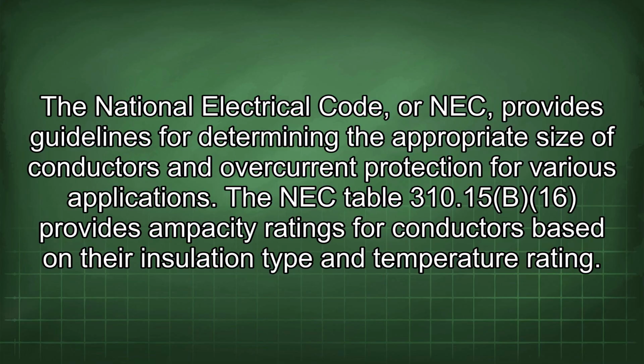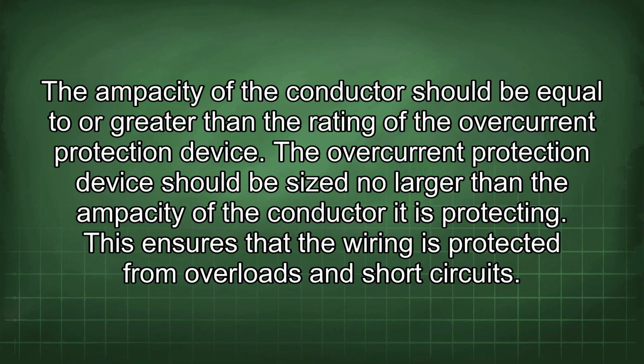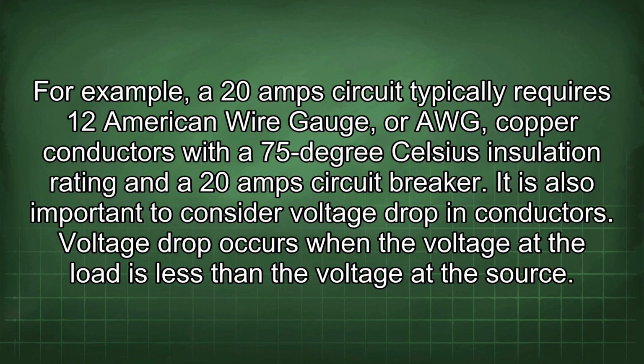310.15(B)(16) provides ampacity ratings for conductors based on their insulation type and temperature rating. The ampacity of the conductor should be equal to or greater than the rating of the overcurrent protection device. The overcurrent protection device should be sized no larger than the ampacity of the conductor it is protecting. This ensures that the wiring is protected from overloads and short circuits. For example, a 20 amp circuit typically requires 12 American Wire Gauge, or AWG, copper conductors with a 75 degrees Celsius insulation rating and a 20 amp circuit breaker.